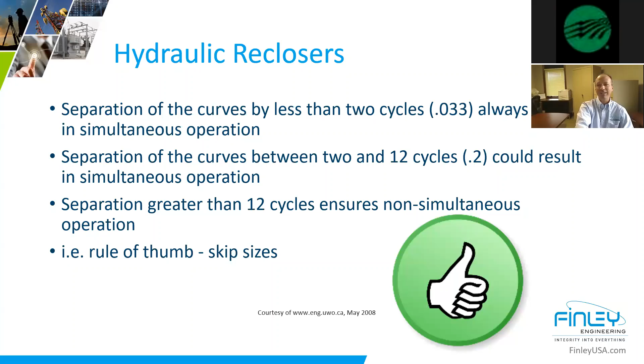And they do work. They've worked for decades, frankly. But here's an interesting statistic. The reason we tend to skip sizes, like going to 100s at the sub, then maybe jumping from 70s to 50s, and then maybe to 25s, is because skipping sizes ensures non-simultaneous operations with standard devices. Because if you get too close, anything less than 2 cycles is going to be simultaneous. A lot of people don't realize that, but that's why that's there, and anybody that does time studies obviously knows that.